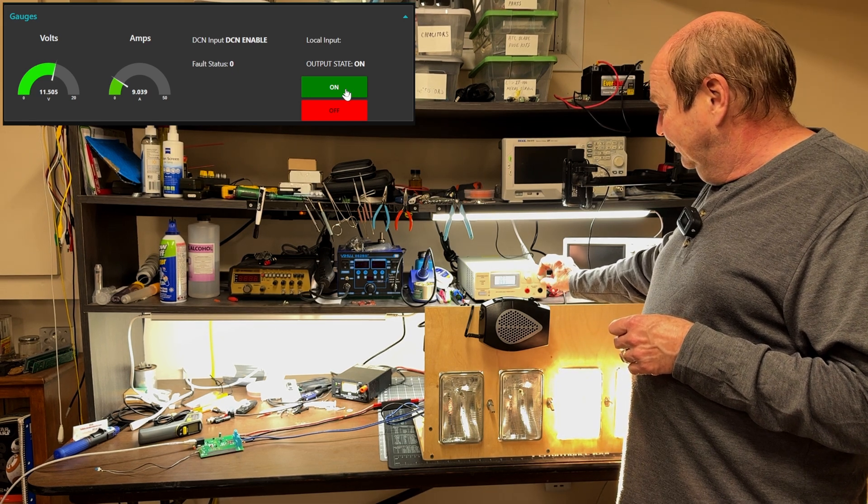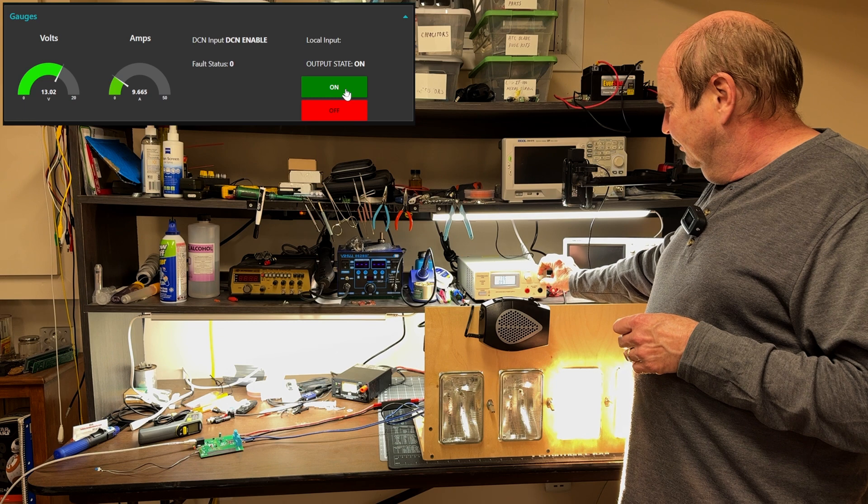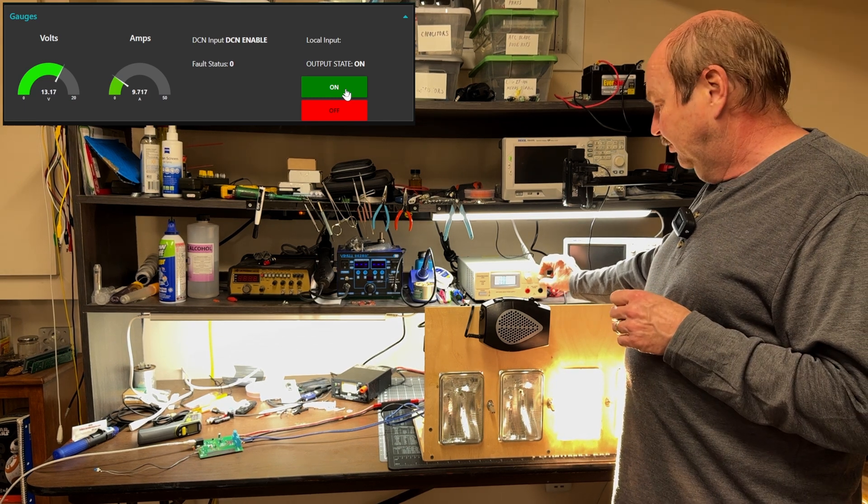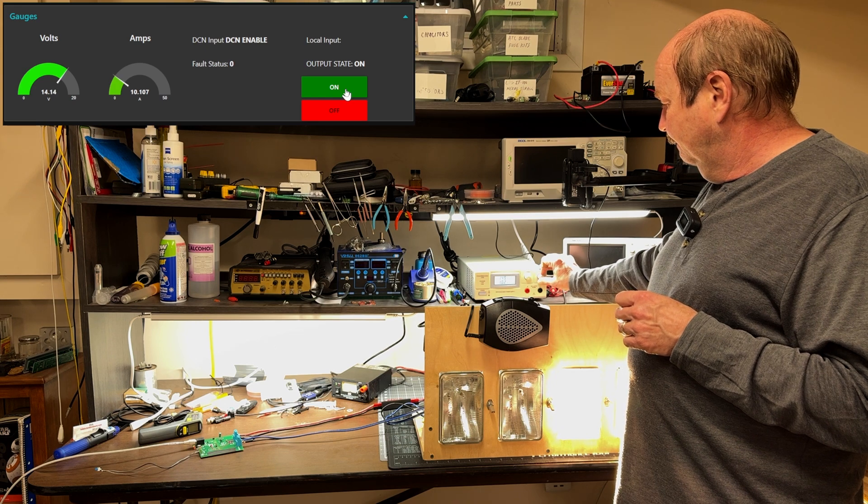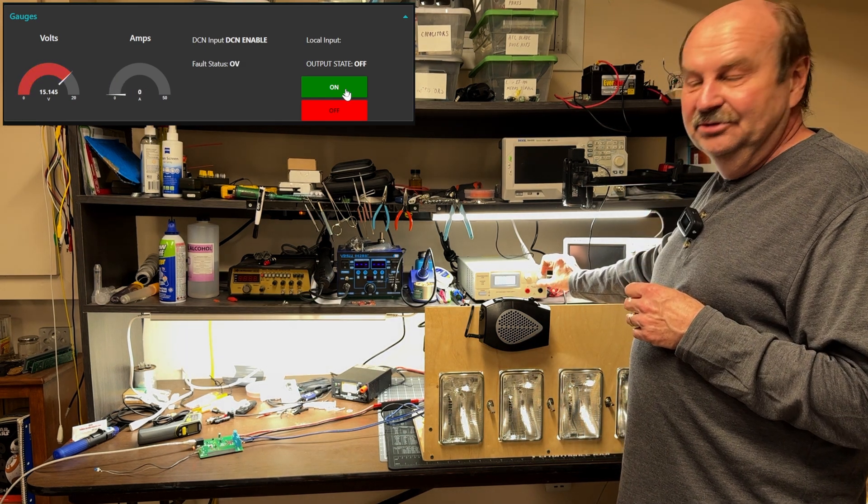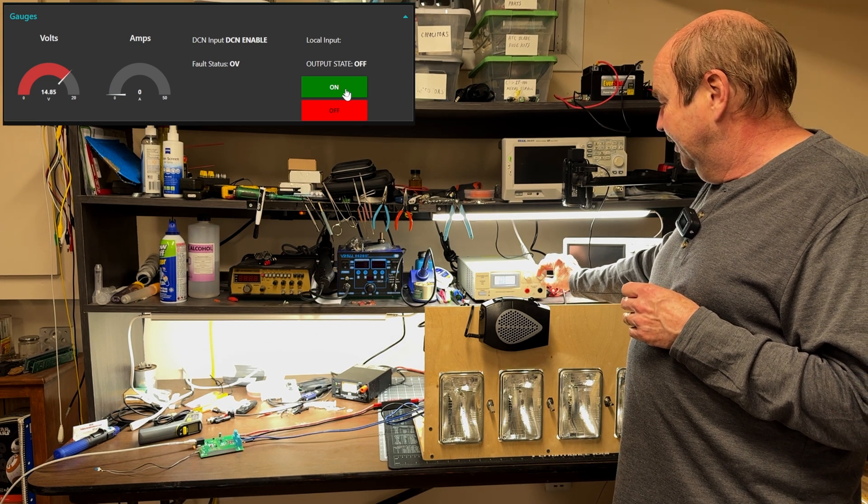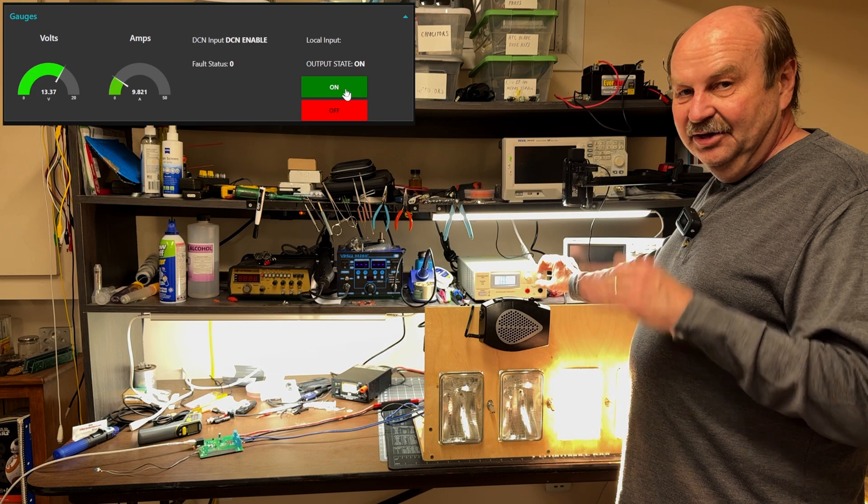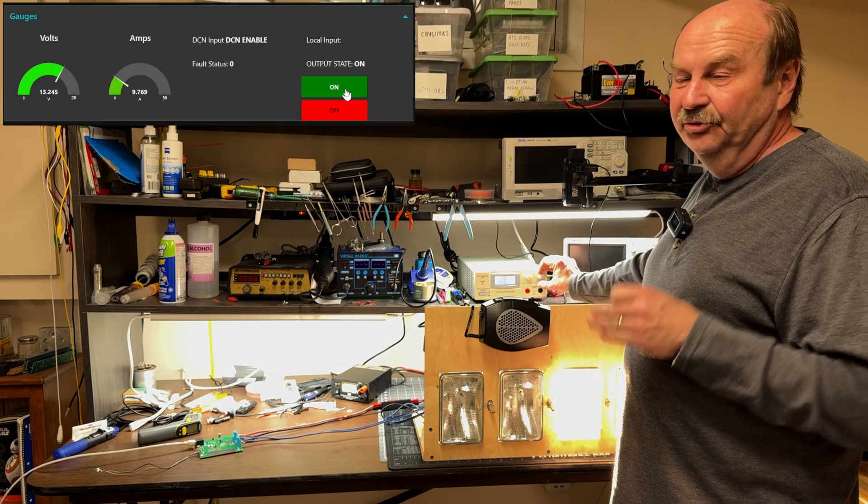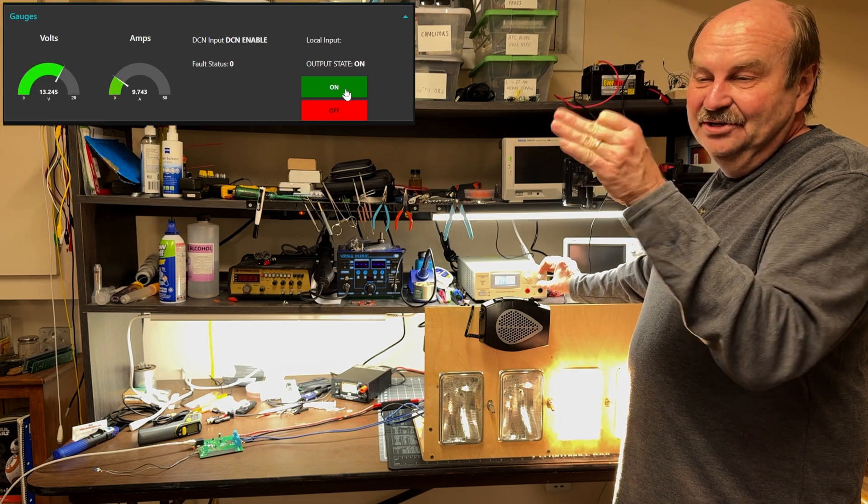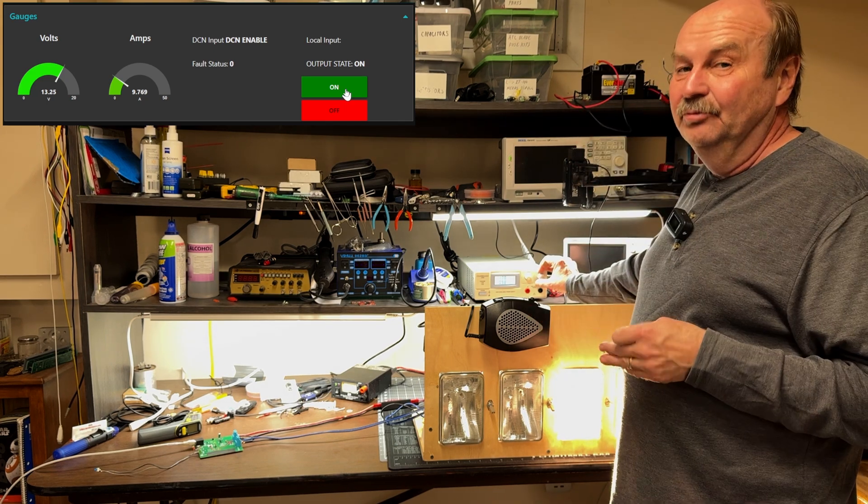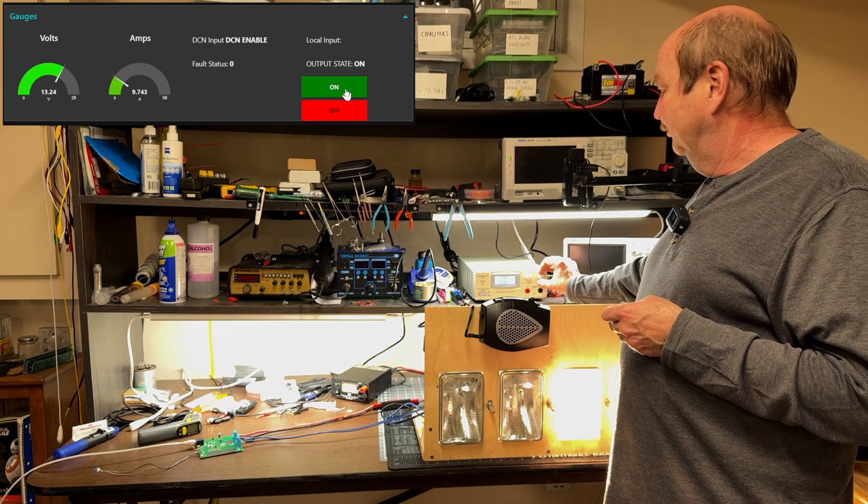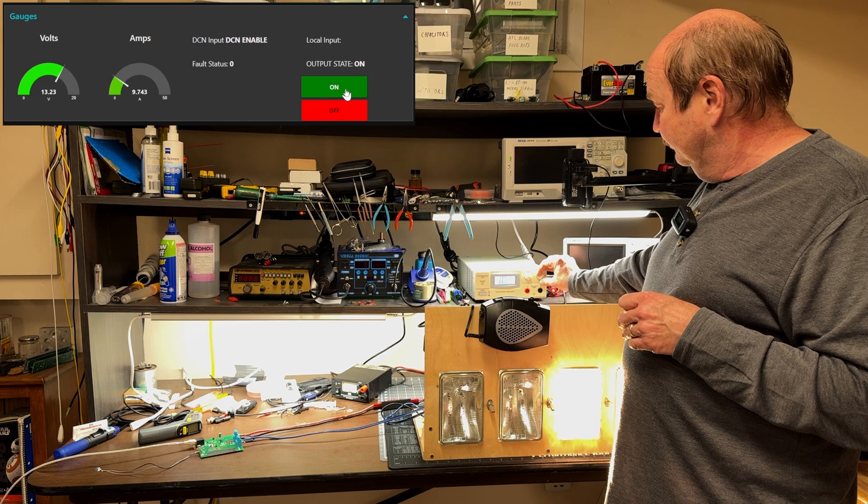And then, if I take the voltage up, I think I have the over voltage set for 14.5 volts. And, when it hits the trip voltage, it shuts off. So, if I bring the voltage back down, then it'll come back on. And, I do have a little bit of about a half a volt of hysteresis in that, so that if you're right on the hairy edge, it's not going to keep tripping on and off. It has to go about a half a volt below the over voltage trip, and it has to come up a half a volt above the under voltage trip.